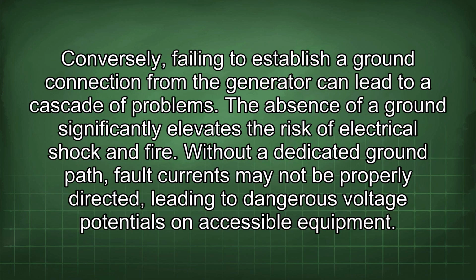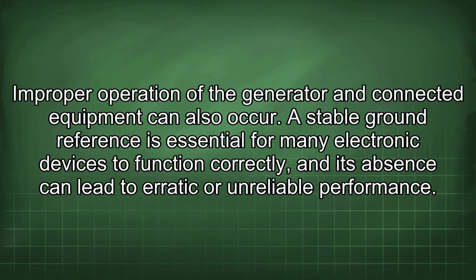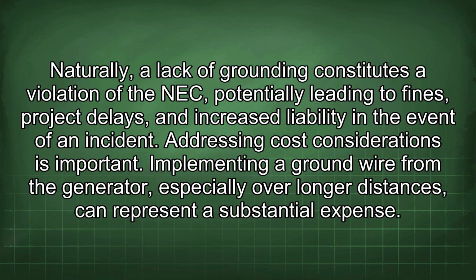Conversely, failing to establish a ground connection from the generator can lead to a cascade of problems. The absence of a ground significantly elevates the risk of electrical shock and fire. Without a dedicated ground path, fault currents may not be properly directed, leading to dangerous voltage potentials on accessible equipment. Improper operation of the generator and connected equipment can also occur. A stable ground reference is essential for many electronic devices to function correctly, and its absence can lead to erratic or unreliable performance. Naturally, a lack of grounding constitutes a violation of the NEC, potentially leading to fines, project delays, and increased liability in the event of an incident.